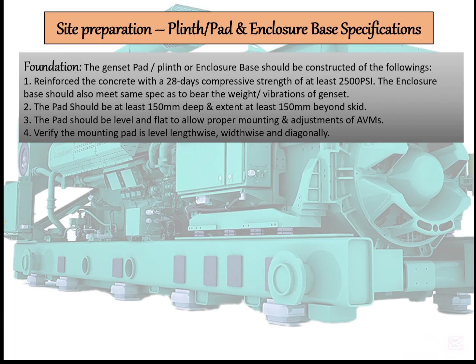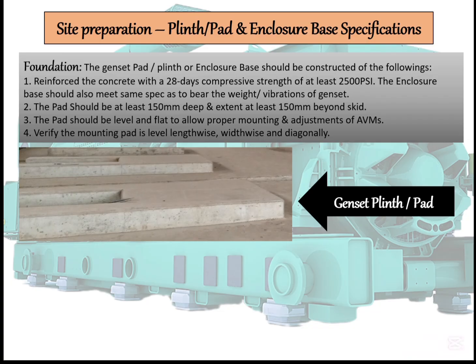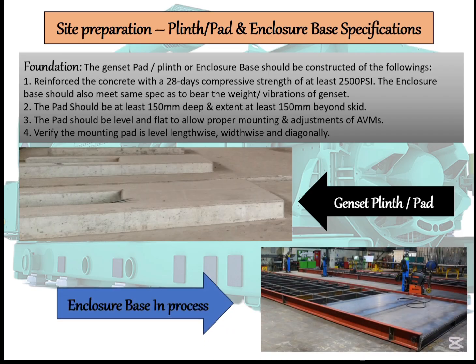Then the recommendation is that your plinth is 150 mm or 6 inches inside the ground and 6 inches above the floor level of your powerhouse, reinforced with concrete and iron parts. And if you are looking at an enclosure, your enclosure or container should have a base strong enough to hold the genset and bear the weight and vibrations during operation. This is the genset plinth inside the powerhouse. You can see it is about 6 inches above the ground floor, 6 inches deep inside the floor, and reinforced with concrete. This is a typical preparation of a container or enclosure, where we have enough iron bars and huge edge beams inside the base, so it can bear the weight of the genset and vibration.